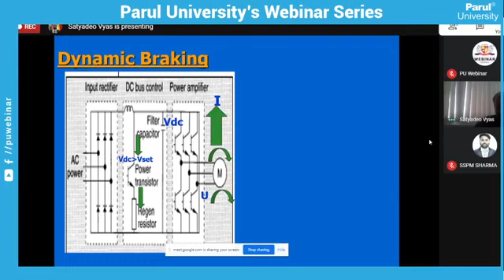then what will happen? The controller will issue the command to the IGBT. The IGBT will start conducting, and that regenerative energy will get dissipated in the resistor. This is the dynamic braking of the motor through VFD.